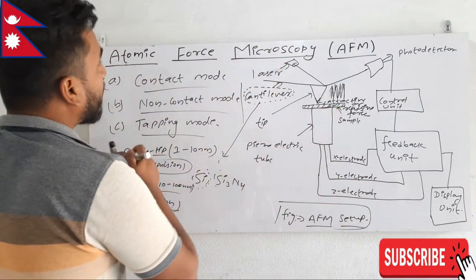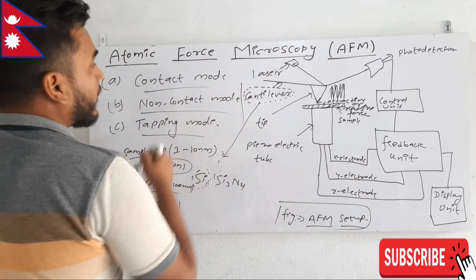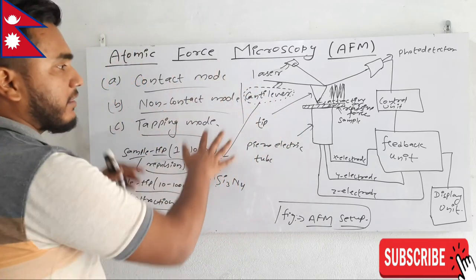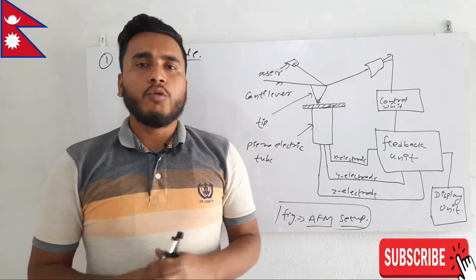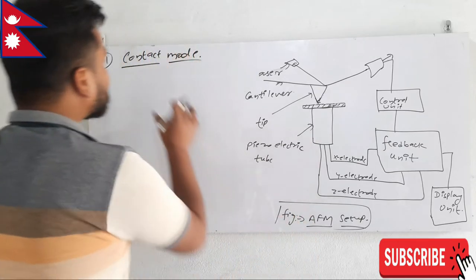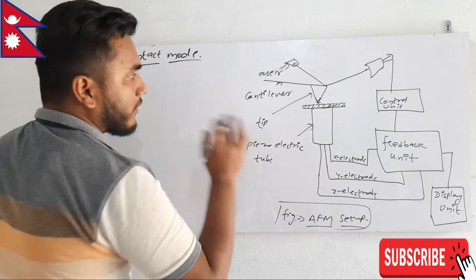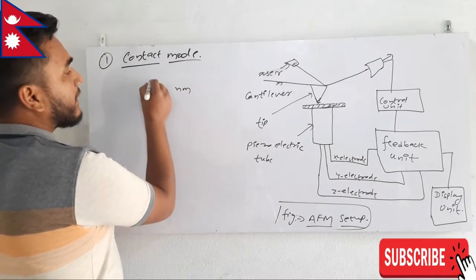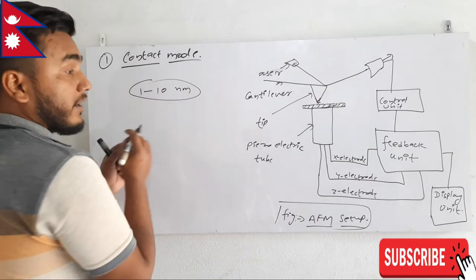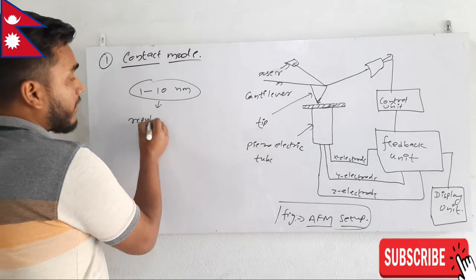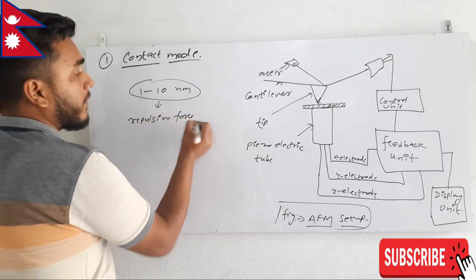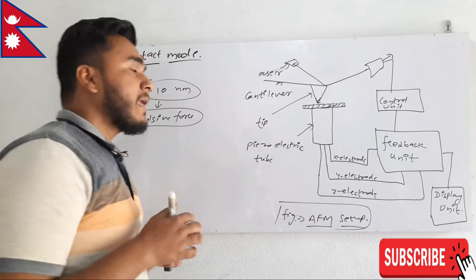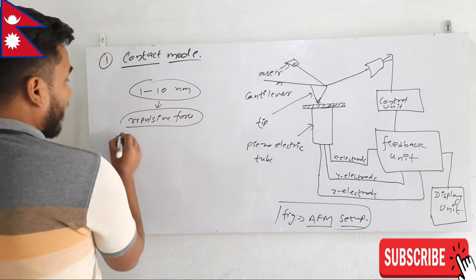Now let us see about contact mode. In contact mode, the tip and sample distance is roughly between 1 to 10 nanometers — they are very close to each other — and due to the closeness there will be repulsive force between them. Contact mode can be executed in two different ways: the first is constant height mode, and the second is constant force mode.